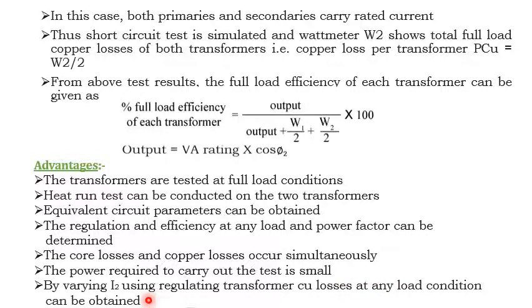So by varying I2 means what? So we inject whatever voltage is to be injected by the low voltage transformer. So that is to be varied. So once that voltage is varied, the I2 is varying, then the copper losses at any load condition can be determined. This is one more advantage.